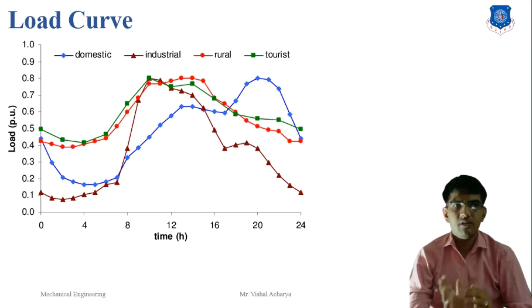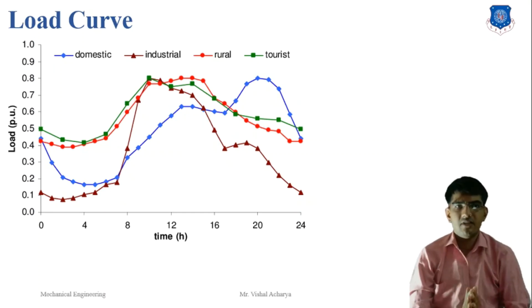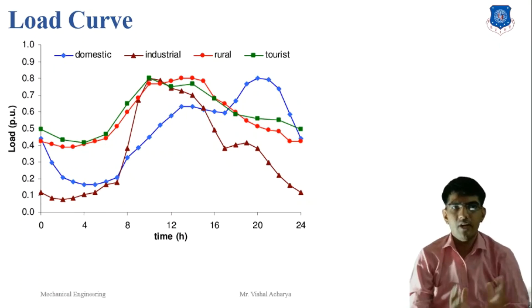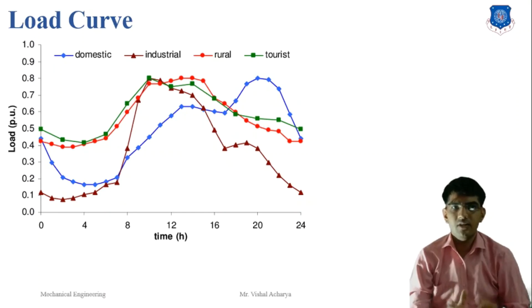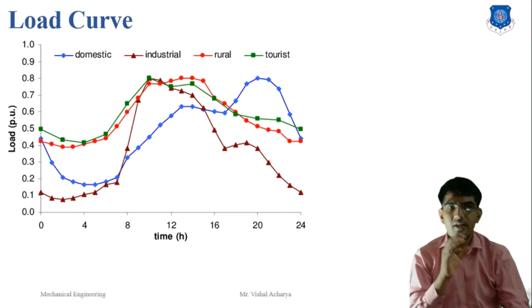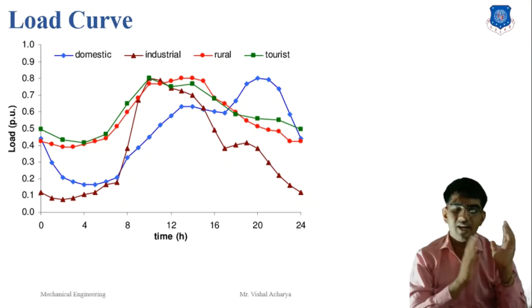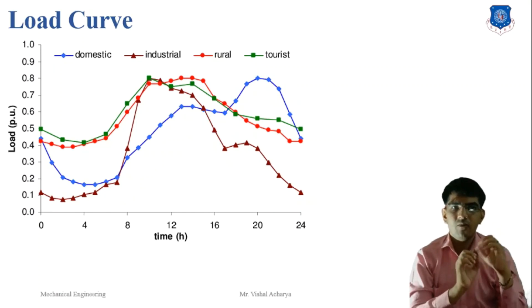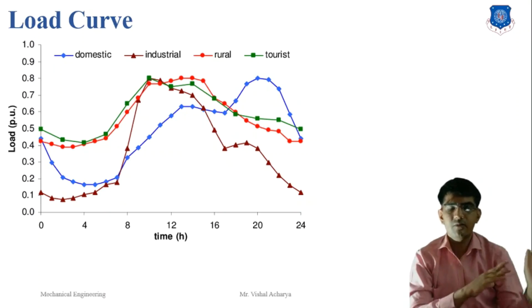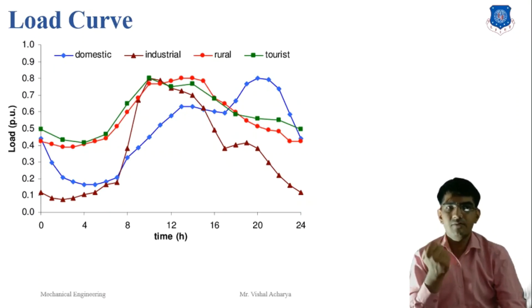It shows the variation of load in the power station. When the load curve is plotted for 24 hours in a day, it is called the daily load curve. If one year is considered, it is called the annual load curve. The load curve of the power plant is not the same for all days — it is different from day to day and season to season. The load curve is mainly classified into two types: summer and winter load curves.